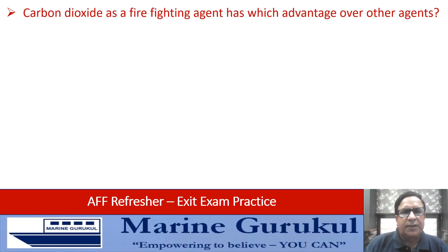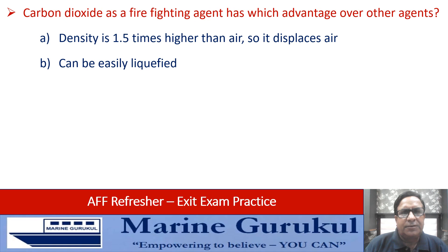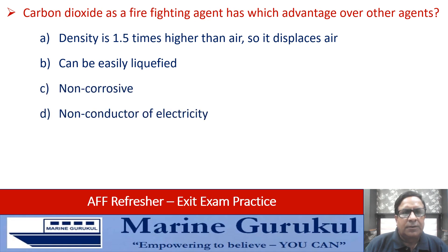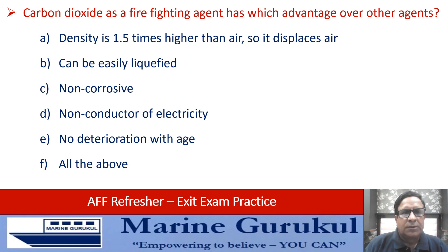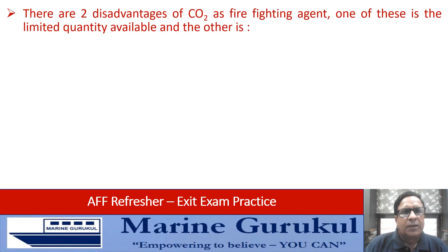Carbon dioxide as a firefighting agent has which advantage over other agents? Its density is 1.5 times higher than air so it displaces air, it can be easily liquefied, it is non-corrosive, a non-conductor of electricity, and has no deterioration with age. All of the above — so the answer is F, all of the above.